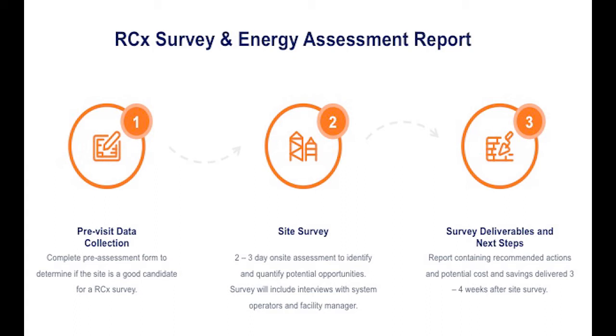For the surveys we typically do for refrigeration systems, there are really 3 main steps in this process. The first step is the pre-site visit data collection, where we send out a spreadsheet questionnaire to the facility asking general information about their equipment—how many refrigeration compressors they have, what size they are, and what the suction and discharge pressures are for the system. We collect this information before visiting the site to validate how much time we need to spend on site evaluating the systems, and to make sure they're a good candidate, or if the system is too small to be worth pursuing under a retro-commissioning process.